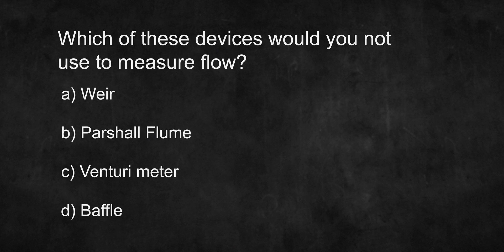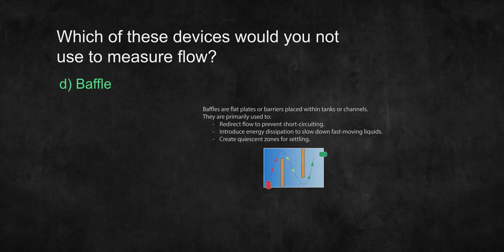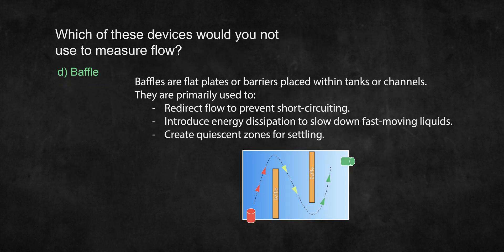Which of these devices would you not use to measure flow? The answer is D: baffle. Weirs, Parshall flumes, and venturi meters are all different types of flow measuring devices — baffles are not. Baffles are used to change the flow pattern and behavior of a liquid, but they are not designed to directly measure the flow rate of a liquid.